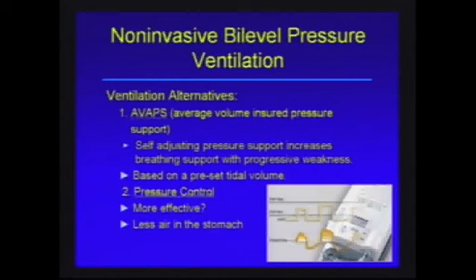So you could try this as an alternative to the bilevel pressure mode, but I'll not say anything more than that for lack of good experience. So moving on to volume cycle ventilators. These are examples of smaller, lighter ventilators that are available today. The trend in the newer ventilators is to have a larger internal battery that allows the ventilator to operate without the need for a dedicated power source. And this is particularly important for portable support.